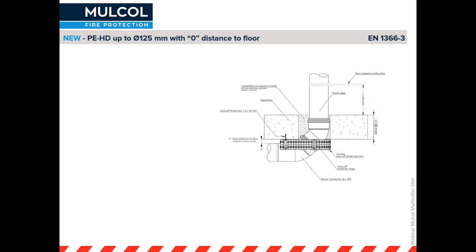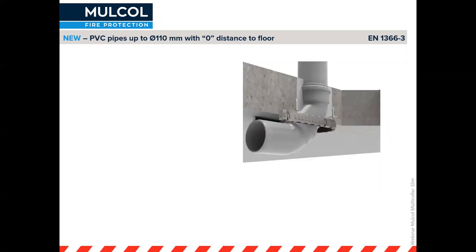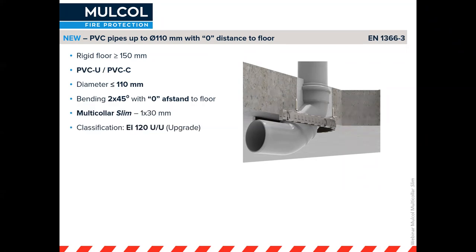For an HDPE pipe of 125 millimeter through the floor at an elbow, it's impossible to get a full collar around it, and the gap is filled with multi-mortar. Because of the larger gap through the opening, you will need two collars, giving 60 minutes uncapped-uncapped — suitable for rainwater and vented waste pipes open to the outside. Similarly for a PVC pipe of 110 millimeters in the same close-to-soffit situation, a single Multicollar Slim achieves 120 minutes uncapped-uncapped — particularly useful in parking garages where maximum headroom is needed.